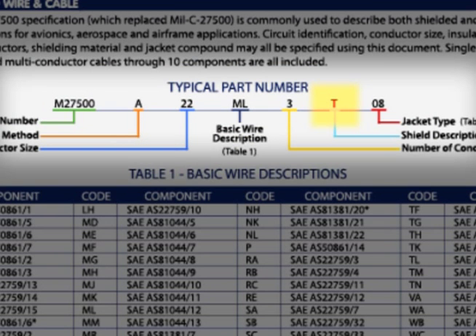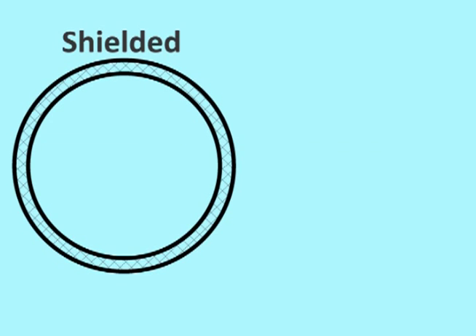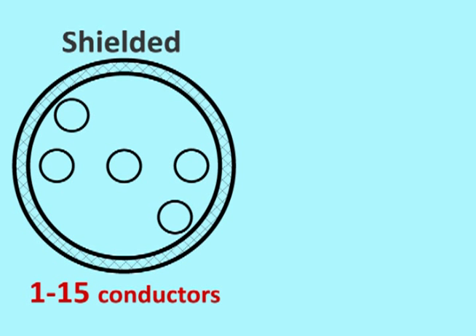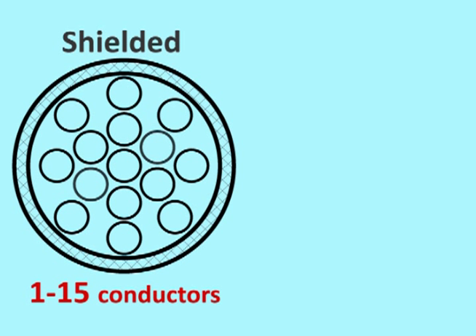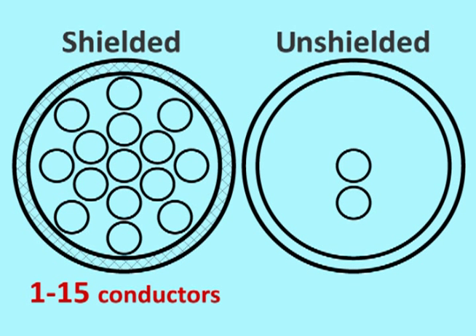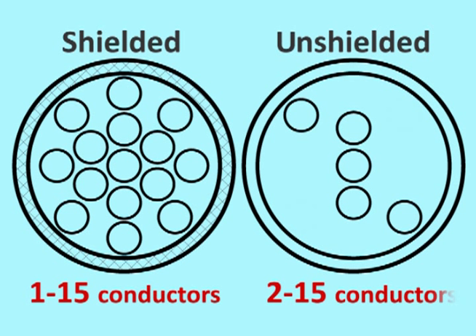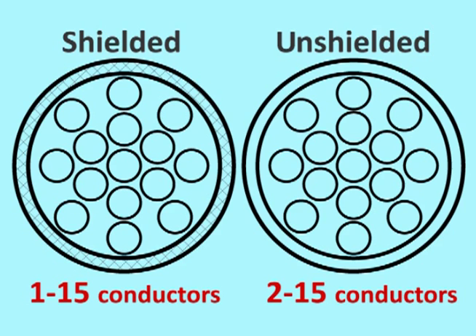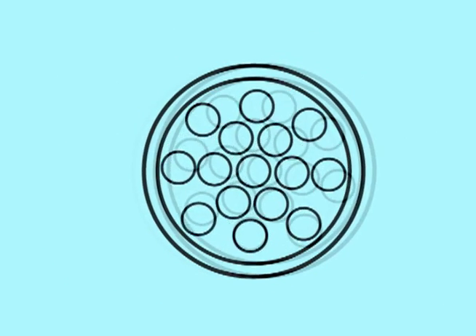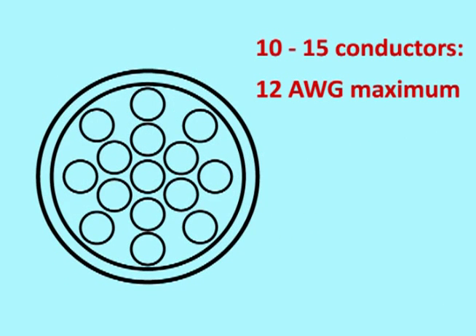The number of conductors is also found in the part number. Shielded cables can have from 1 to 15 conductors. Unshielded cables can have between 2 and 15 conductors. If a cable has 10 to 15 conductors, they may be no larger than 12-gauge.